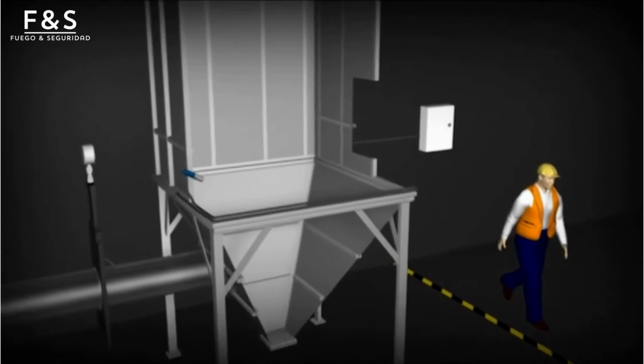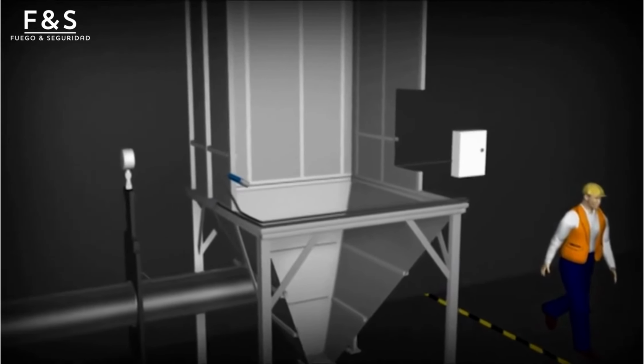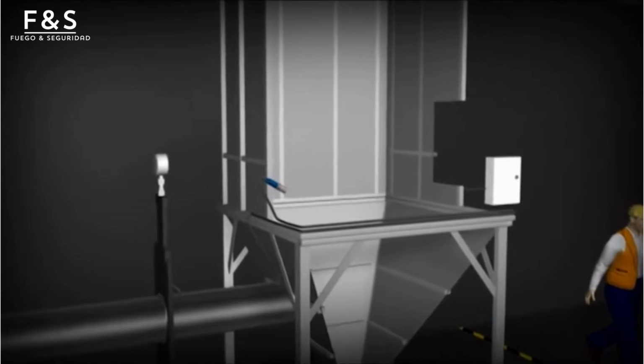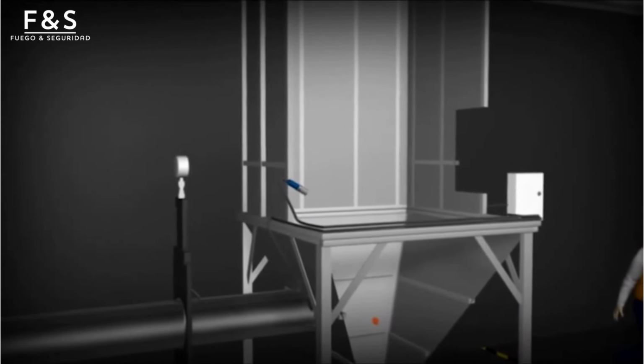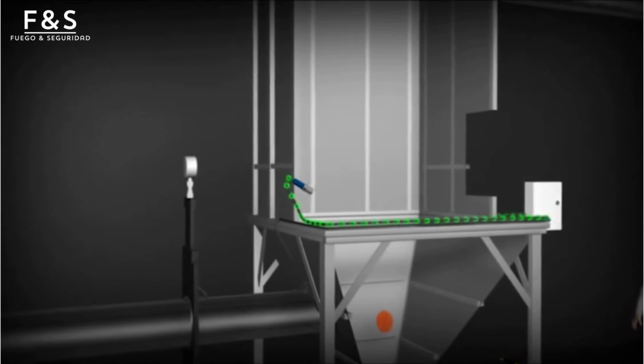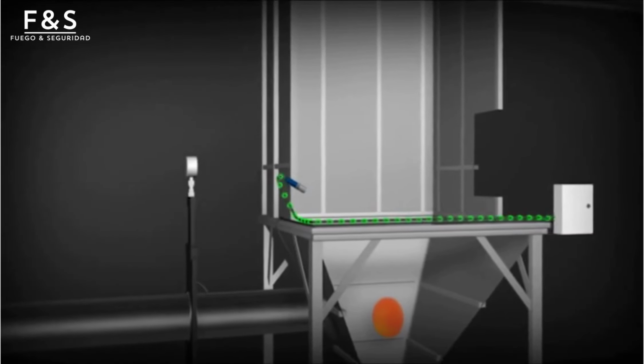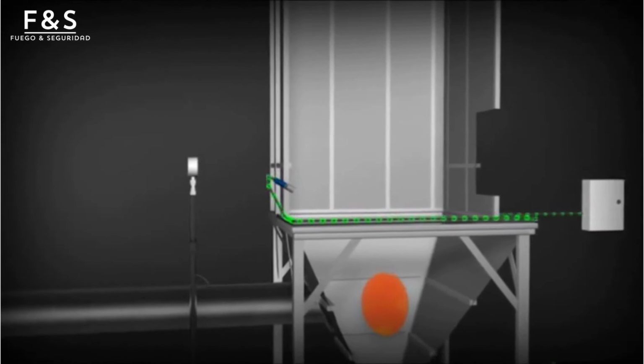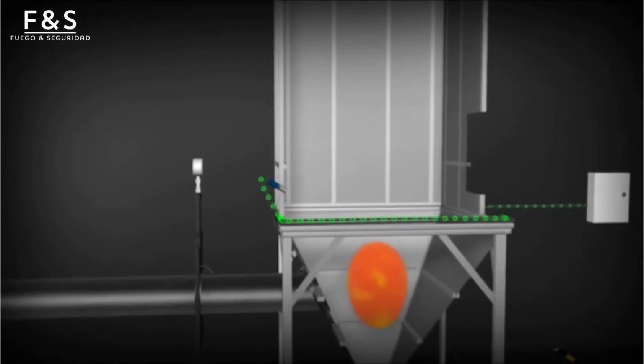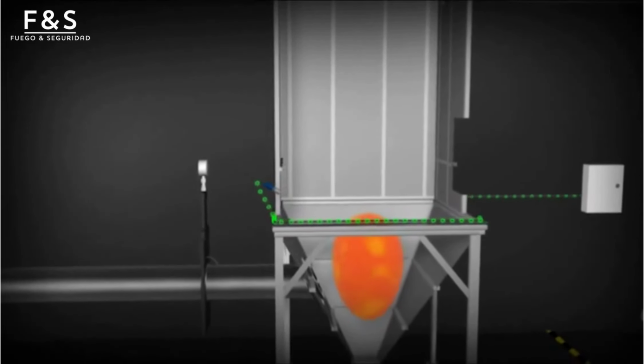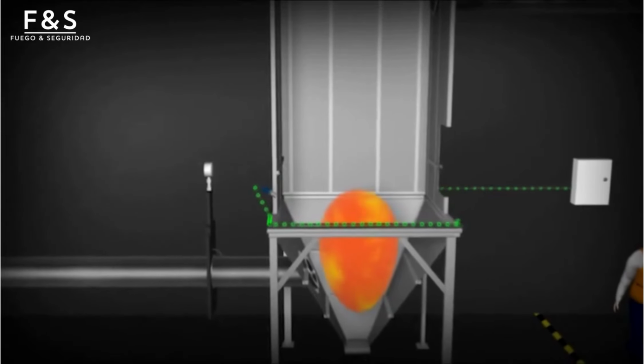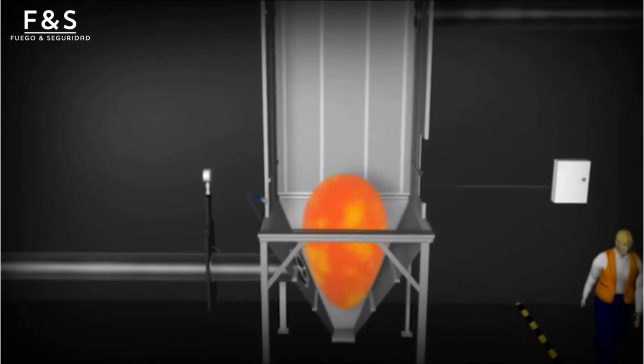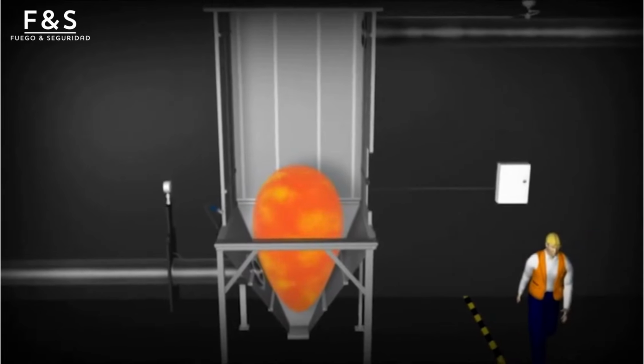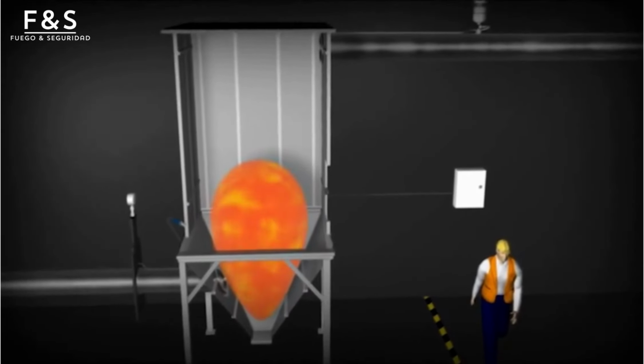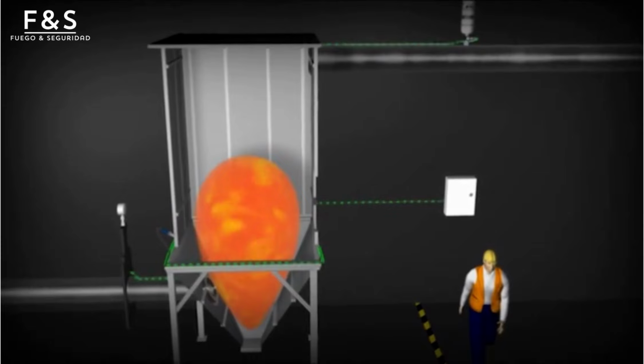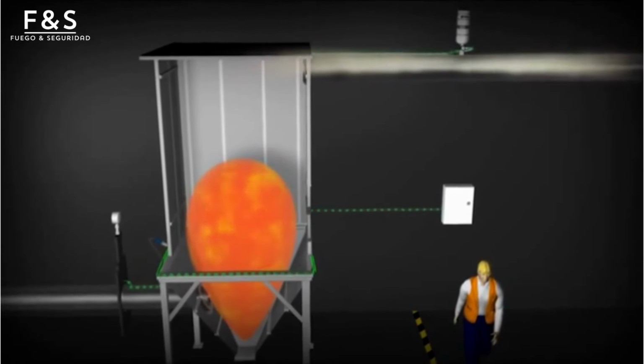During a deflagration, the pressure wave from the explosion reaches the detector connected to the explosion protection control panel, which processes 4,000 data points per second. The system alarms at a preset pressure level and sends an activation signal to the isolation devices. The system opens a rupture disk on an isolation container that uses 500 psi of nitrogen to drive suppressant into the ductwork, providing a chemical isolation barrier that prevents the propagation of the explosion.